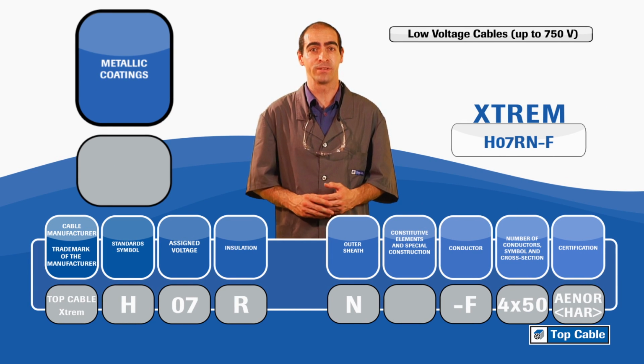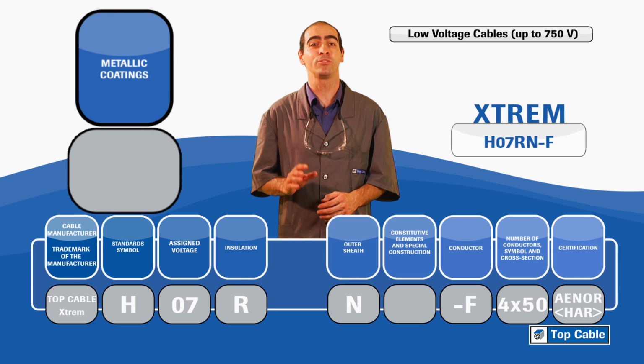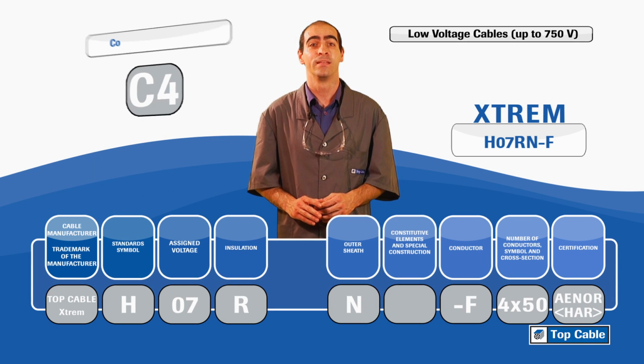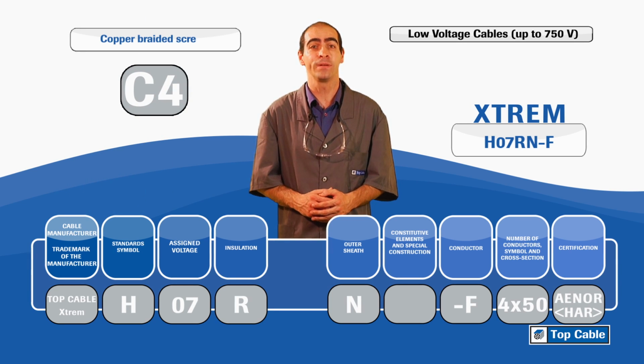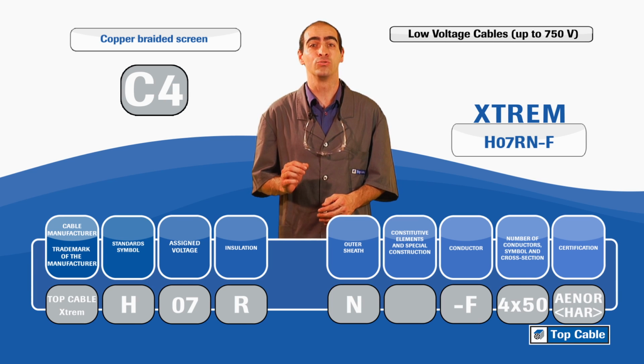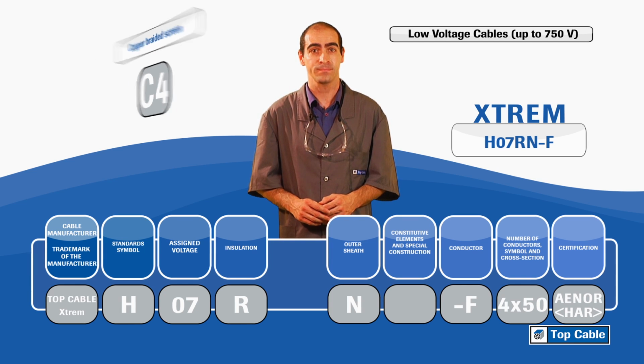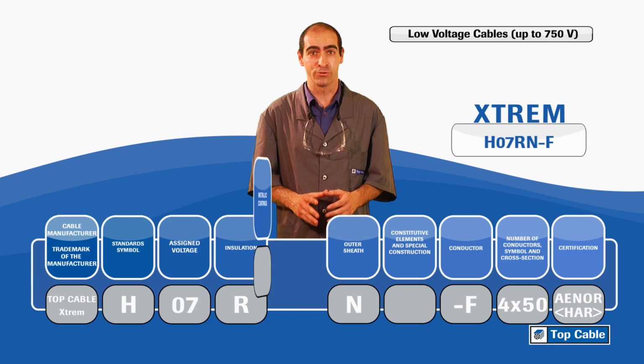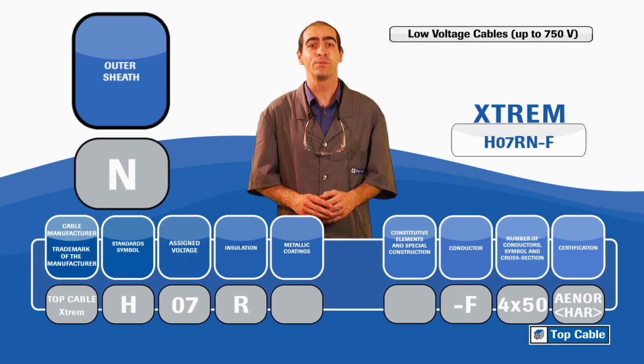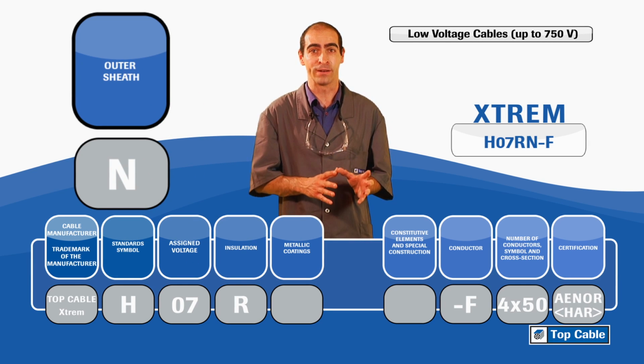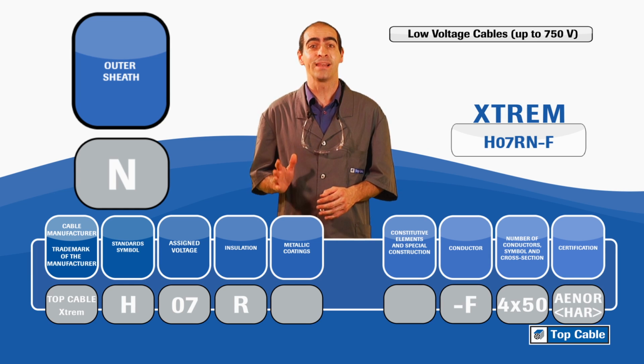H07RN-F is not reinforced with any metallic coatings. The most common metallic coatings are C4, copper braided screen. Xtrem H07RN-F's outer sheath is made of polychloroprene, as is indicated by the letter N.